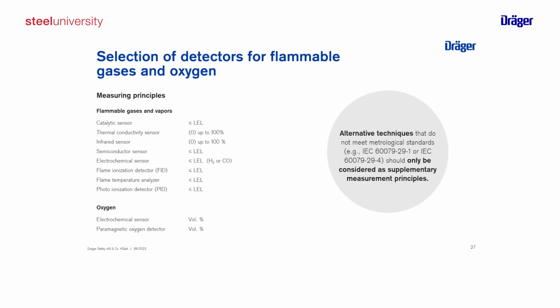You can also use FID or PID, but this is, I would say, not typical for the primary explosion protection. What is important to know is if there are new technologies stepping into the market, like ultrasonic leak detection, IR cameras, etc., you can use this, but only as supplementary. So this can't replace your safety concept, which is based on certain detectors like here. You can't replace this with the alternative, but you can add, for example, an ultrasonic gas leak detector, to have a higher reliability of your system.